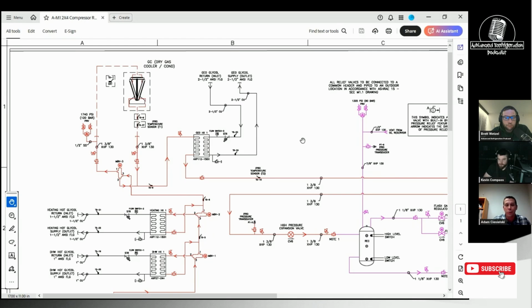And I know you don't want to do that, but even that little bit from 10 to 0%, if you run it, you can basically straight line the gas cooler control. If you don't, then the fans will turn on and off, and you'll get a saw blade effect. And albeit it's horrible, but if the tuning of the fans is too aggressive, then things can get out of control quickly. Yeah, I've never seen the LLCM mode work, but it's always been a thing of, if you don't have a stable control signal, then it doesn't function properly.